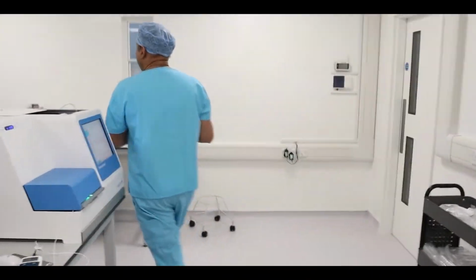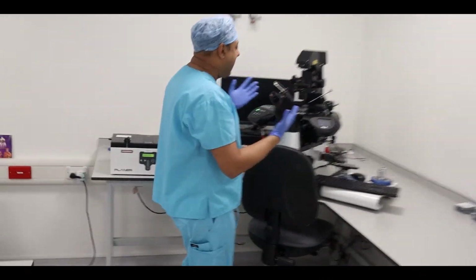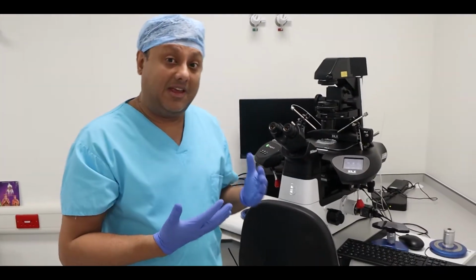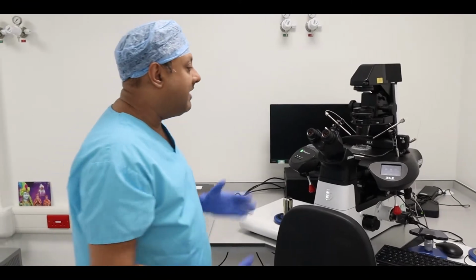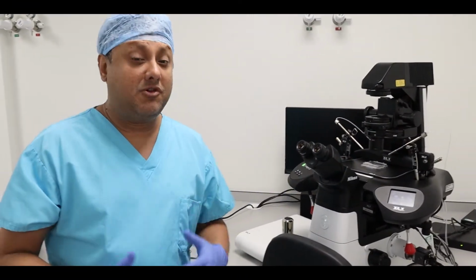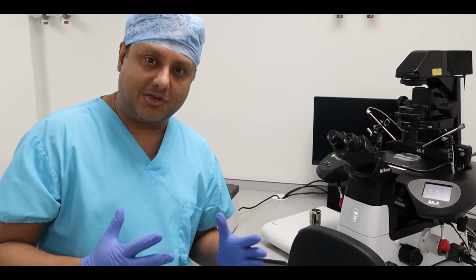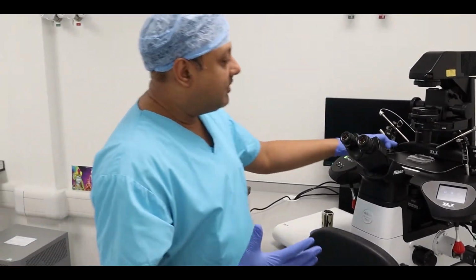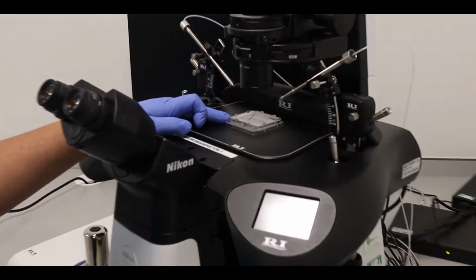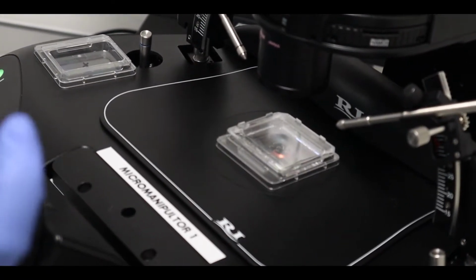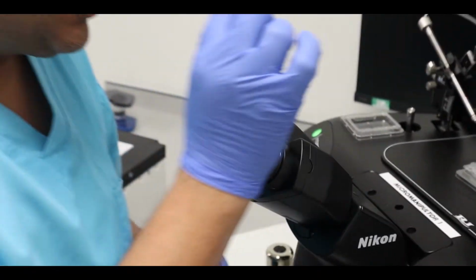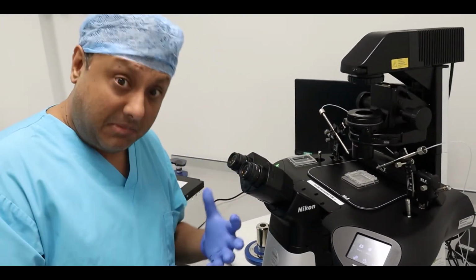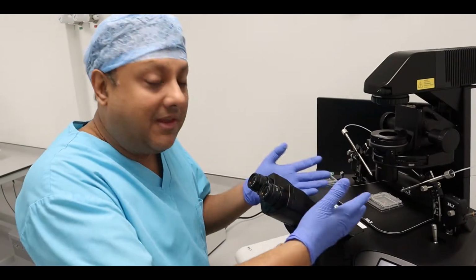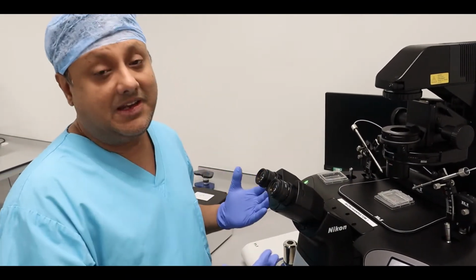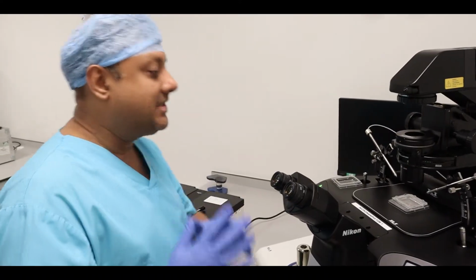I'll take you through here on the micromanipulator. This is where the eggs are injected when we're doing ICSI or when we're biopsying the embryos as well. And again, as I said, the eggs and embryos have to be kept under very physiological temperature conditions, which is around 37. So here we have a dummy dish because I'm doing some checks on there. And the way we measure the temperature is we'll put a very tiny probe, a thermometer probe in there, sitting in each and every one of those small drops, mimicking what the embryos are facing when they're being manipulated on the manipulator. And ideally, again, we want a 37.0 degrees temperature.